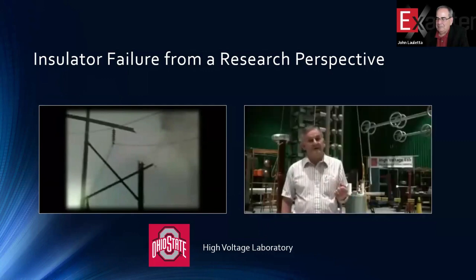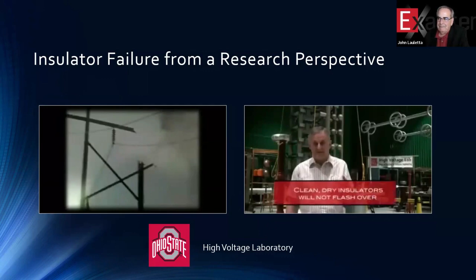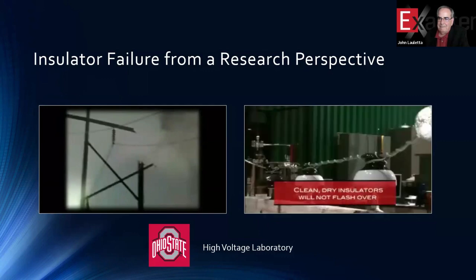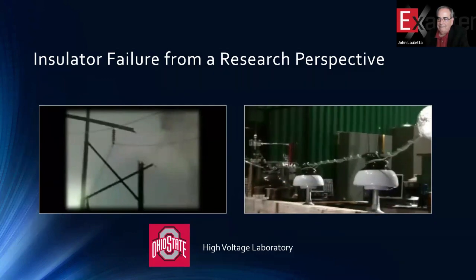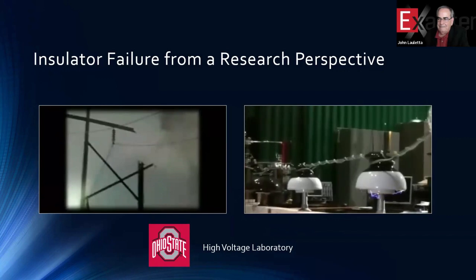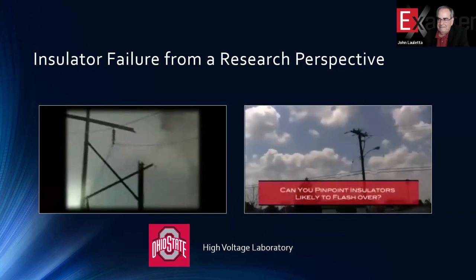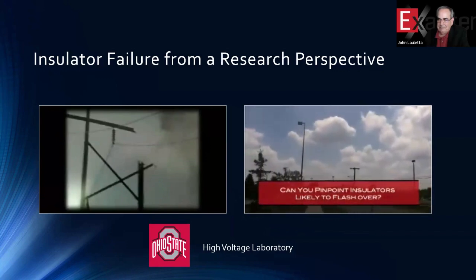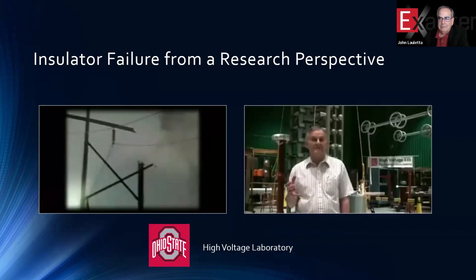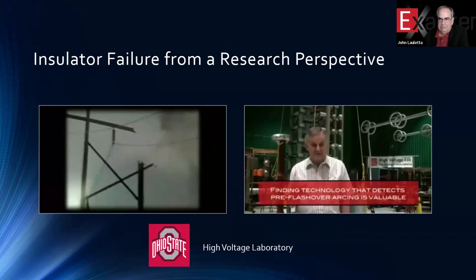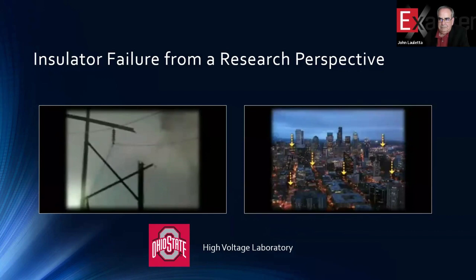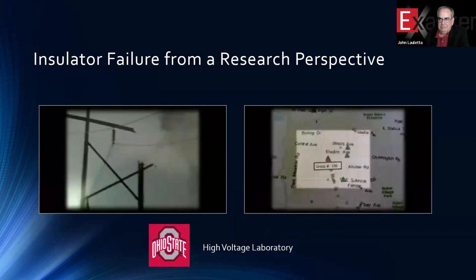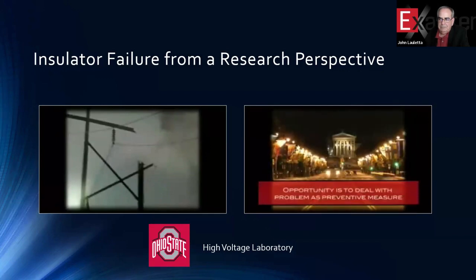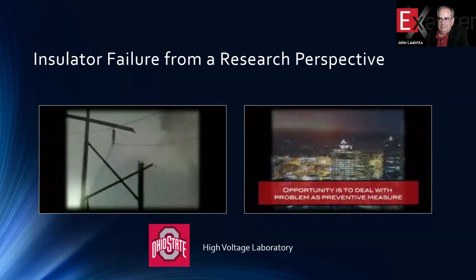The question is, how can you delay this process to keep the insulator cleaner? How can you do that? Uncontaminated, dry, clean insulator would not flash over because the operating voltage is much less than the flashover voltage of the insulator, much less than the withstand voltage of the insulator. But what if you could pinpoint the specific insulators on your system that were most likely to flash over? So if you have any instrument, any system that would be able to detect this type of activity, then the distribution line is still in service, that would be valuable because then it is not an outage type of problem that you have, but it is a prevention type of problem that you have.